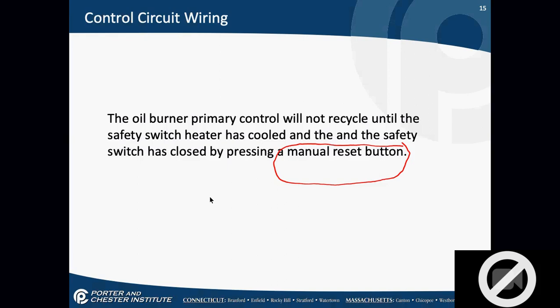What happens when the oil burner tech comes along and eventually fixes the problem after the customer has pressed that safety 20 or 30 times? I assume there's a large cleanup for him. Well, if he notices, there's a relatively large oil cleanup. If he doesn't notice and ignites that burner, there's a relatively large bang, and there's a lot of smoke and soot cleanup that happens, including usually a company that comes in and does the cleanup of the whole house, including repainting.